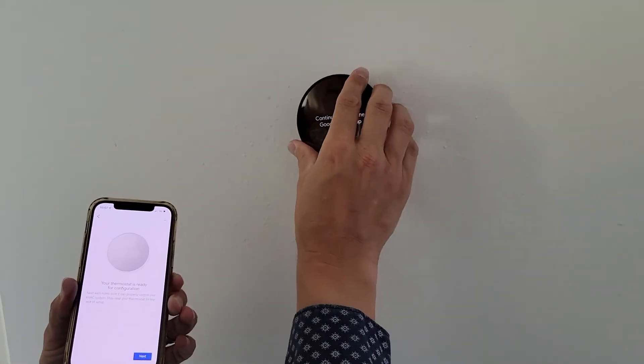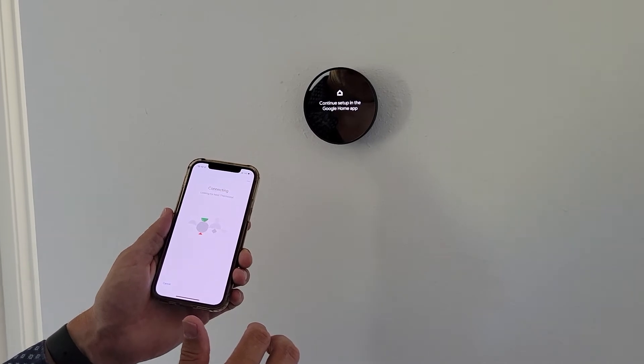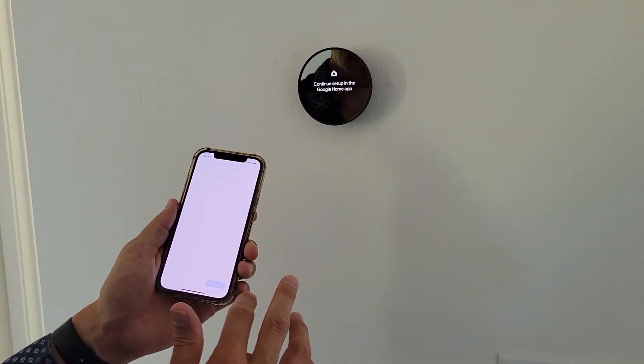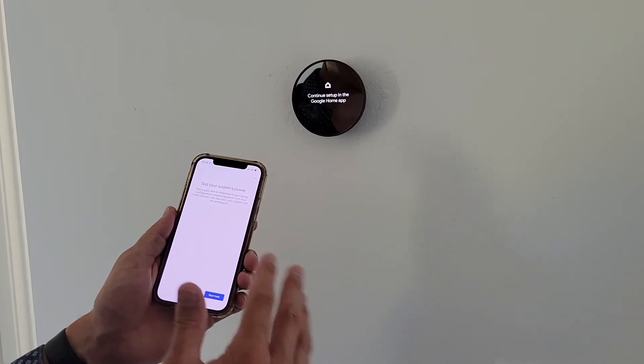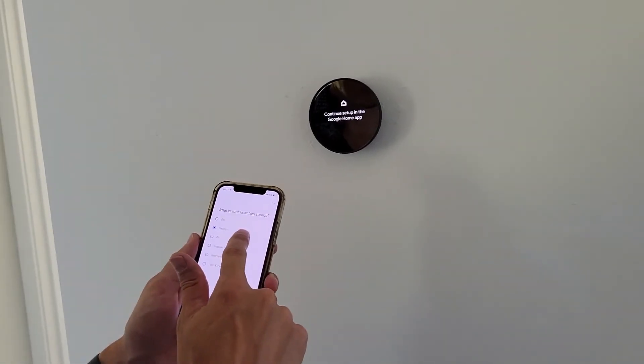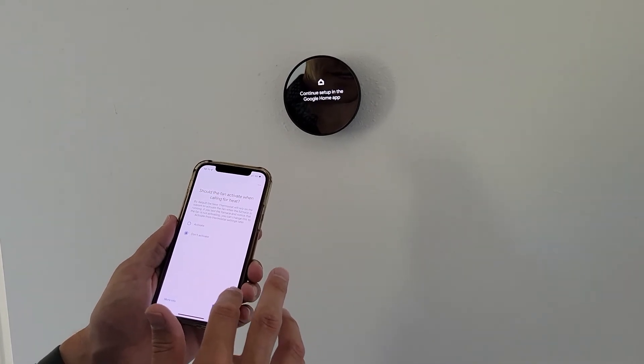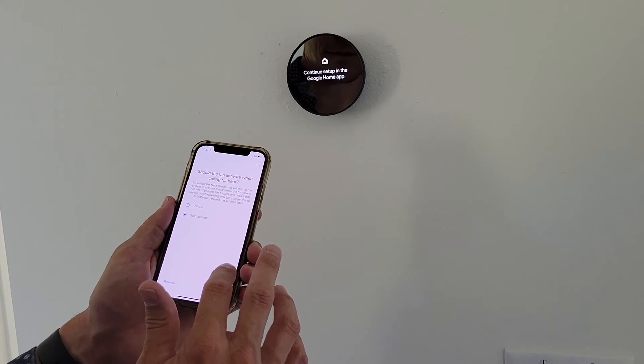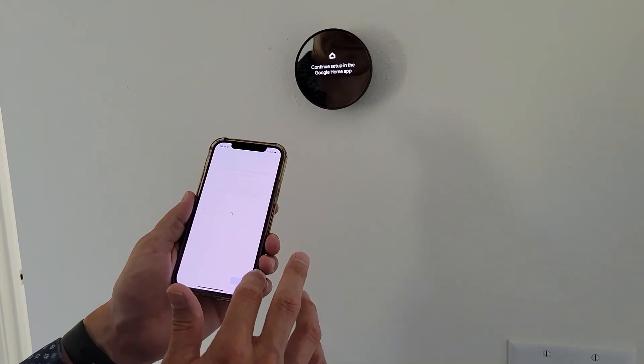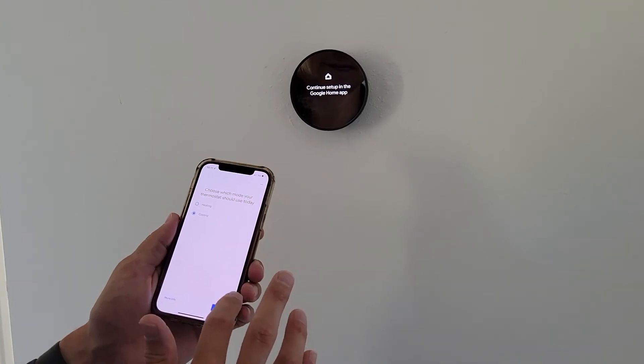Before I go any further I want to put this back on — your thermostat is ready for configuration. I'm going to pick English. Now it wants to test the system power based on the wires I just selected. We've got gas/electric for our source, forced air, and the question is should the fan activate when calling for heat? Since it defaulted to 'don't activate,' I'm just going to leave that. Currently we are in July, so I'm going to set it for cooling.